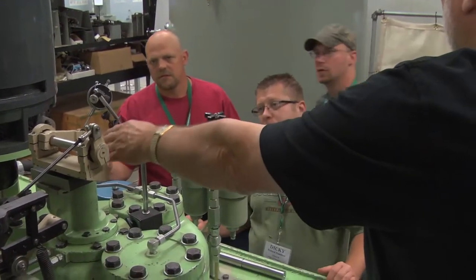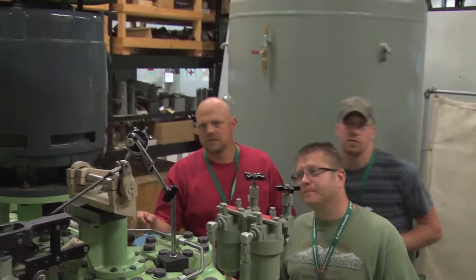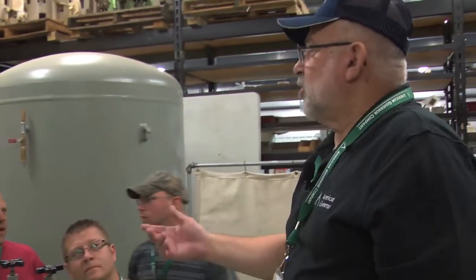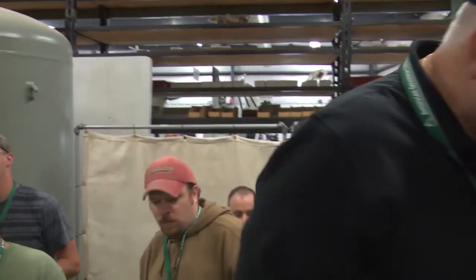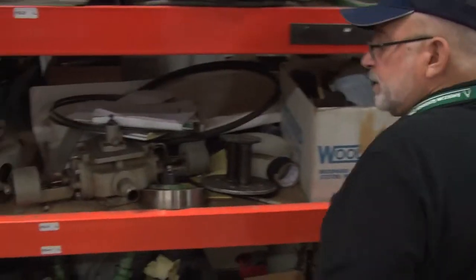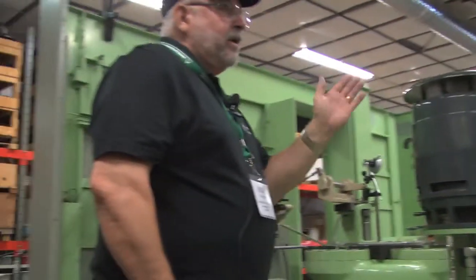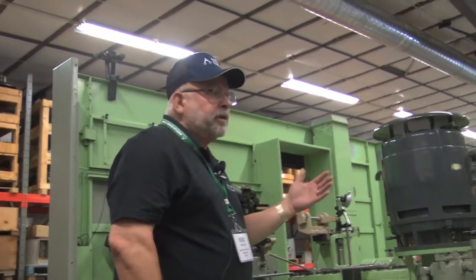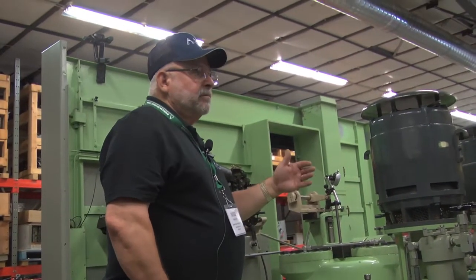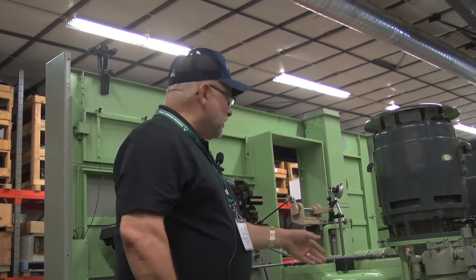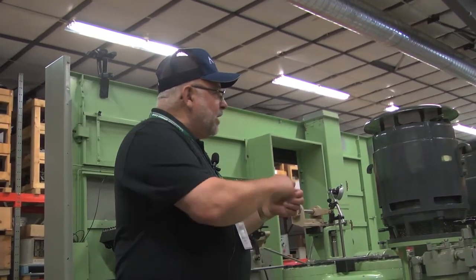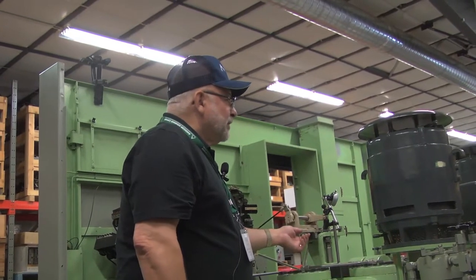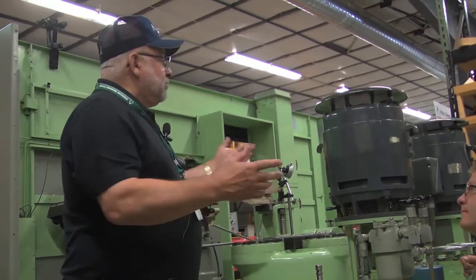And I'm not getting all of it there. Right. Usually like 2,000 to 3,000. You can get 10, 7. That's 4,000. You only get 3,000 or 4,000 travel in one direction. Total up and down should be somewhere around, on a Woodward, 7 to 10. On these I've seen some of them really vibrate. Sometimes the guys took those out and lost those screws, and didn't know it for years.